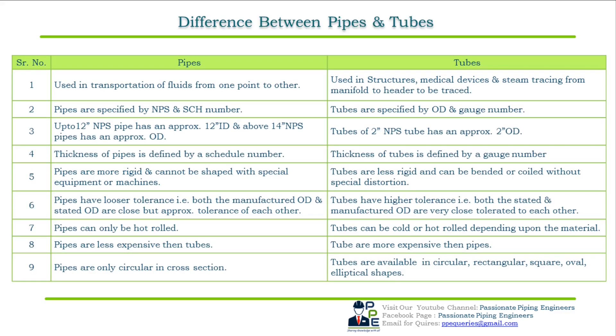Now for the difference between pipes and tubes: Pipes are used in transportation of fluids from one point to another, whereas tubes are used in structural applications, medical devices, and steam tracing from manifold to header. Pipes are specified by NPS and schedule numbers, while tubes are specified by OD and gauge numbers.